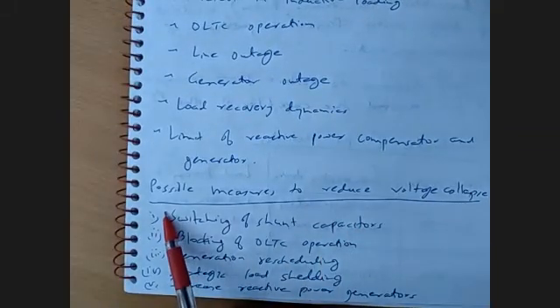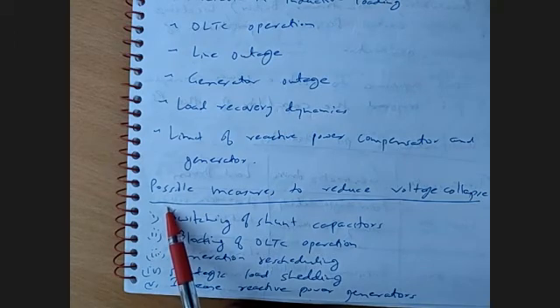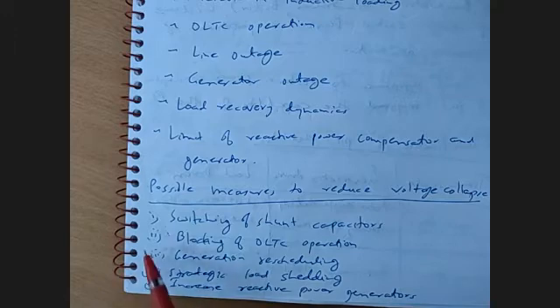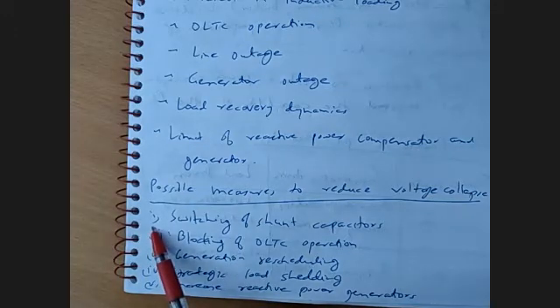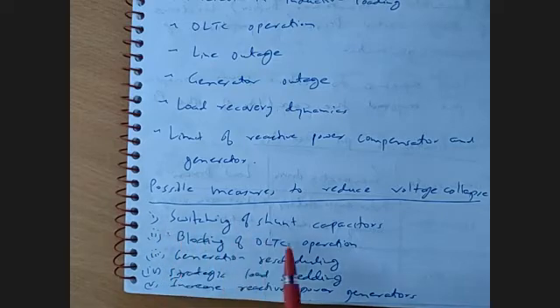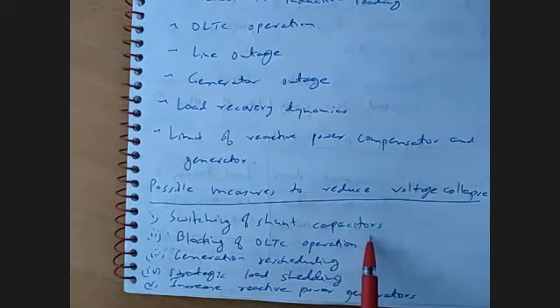So now, what are we doing to reduce the possibility of voltage collapse? First, to reduce the voltage collapse, switching of shunt capacitors is done to increase the reactive power generation in the system.